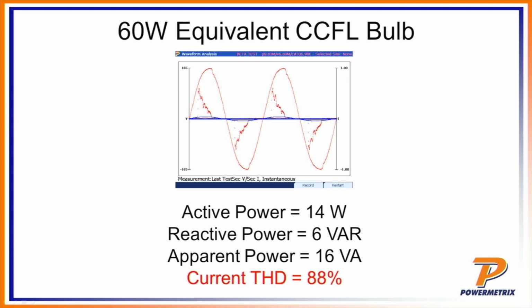If we go to the next example, compact fluorescent light bulb. Once again, this is a 60-watt equivalent, so it's outputting about the same amount of light, which ultimately is what the customer cares about. But what we notice is that we've gone from 40 watts on the incandescent bulb down to now 14 watts. So basically 1/3 of the active power being consumed. So, for the customer, that's a great savings. He's being billed on watt hours, and so if I can replace all the bulbs and basically get the same amount of light out, but only consume 1/3 of the wattage, then that's going to be a great savings. Now, the flip side of that is, for the utility, guess what?